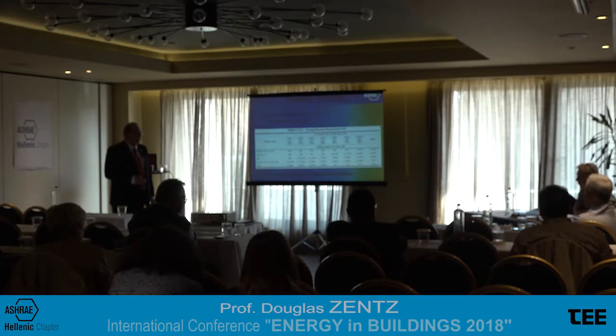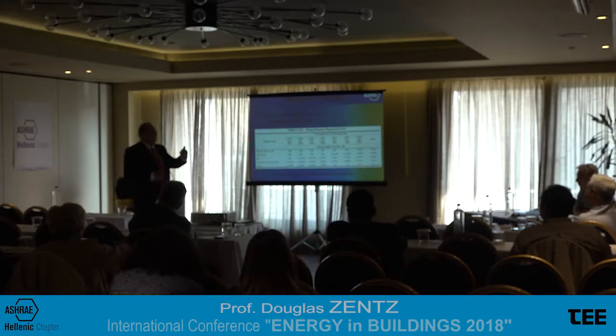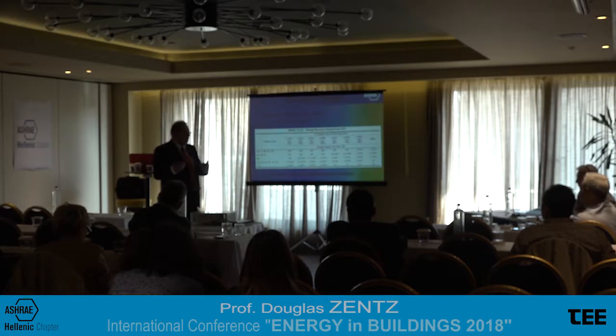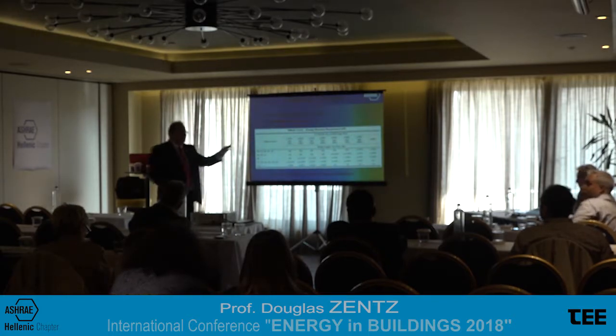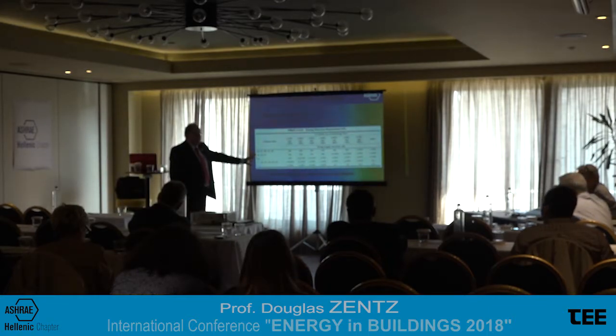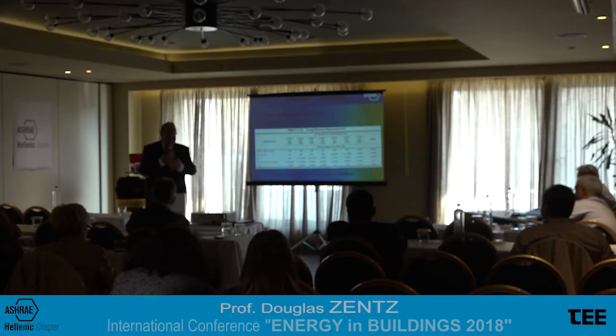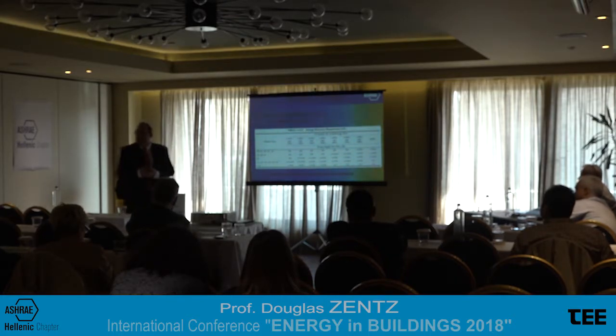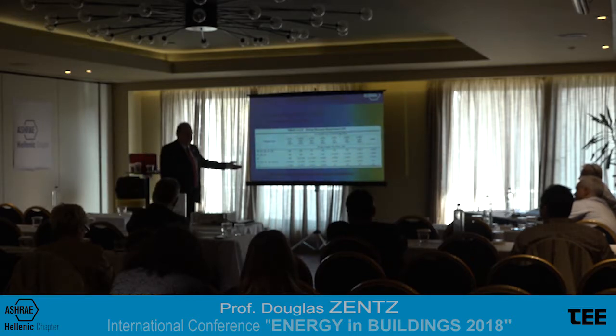The problem is that you cannot always use the exhaust air. I know, it's a big problem because it's different class air and you can't cross-contaminate. I understand that. Hey, the standard is just saying they want you to be conscious about energy recovery. If you can't get to 60%, you've got to use a different tile because of cross-contamination, class 3 air, class 1 air, you can't cross-contaminate. I understand that. It might have to happen. Maybe the best you can get is 48%. And you go, hey, it's the best we can do.